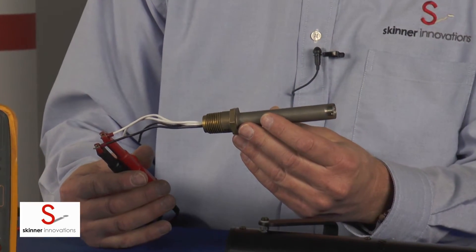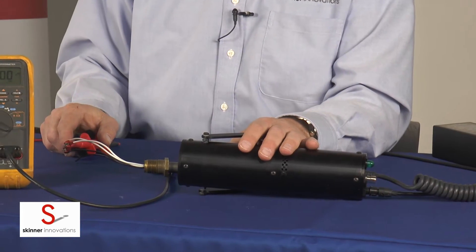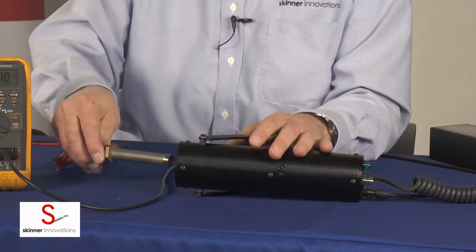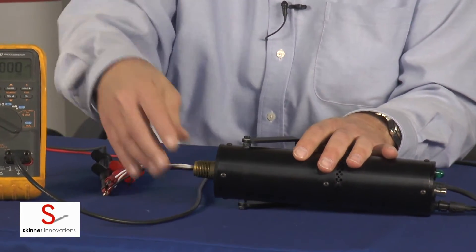Hi, in this video segment we're going to be testing a Fenwal Detect-A-Fire 190 degree Fahrenheit rate compensated heat detector. We're going to be using the HST heat detector tester with standard heating. To do that we'll insert the Fenwal detector into the tester.